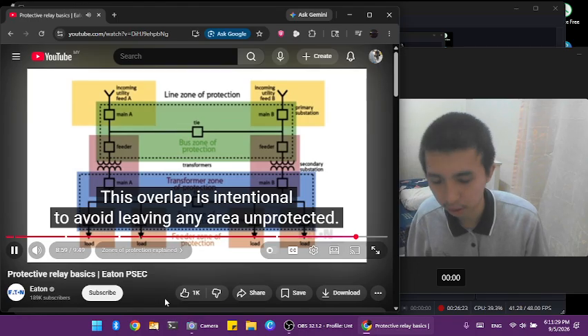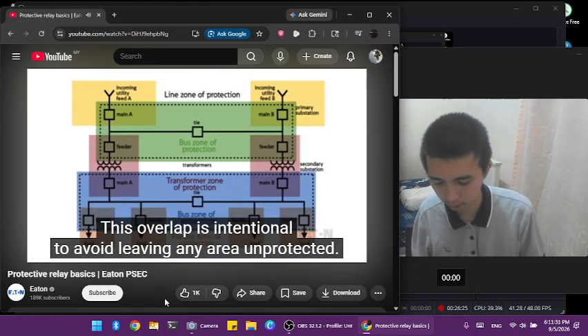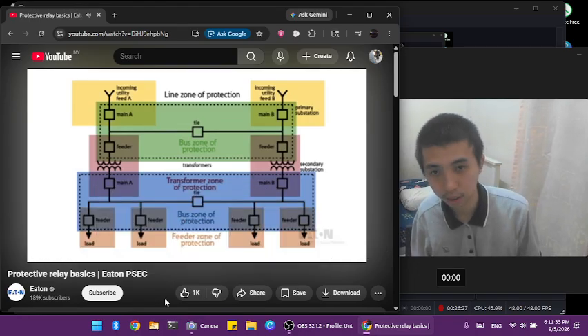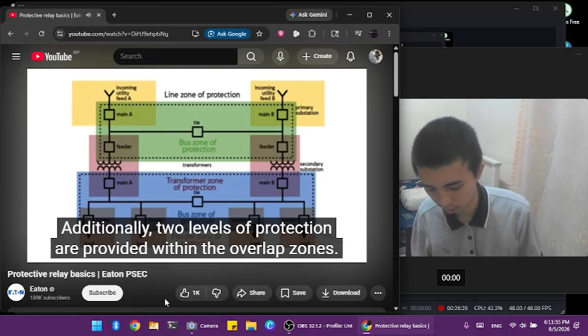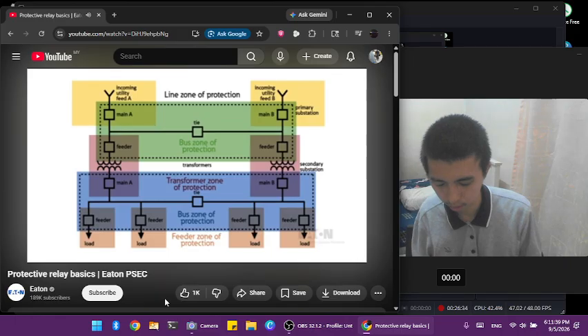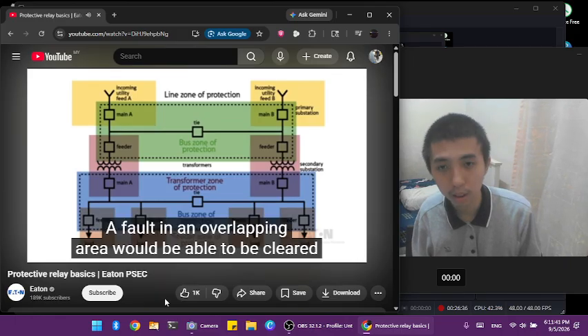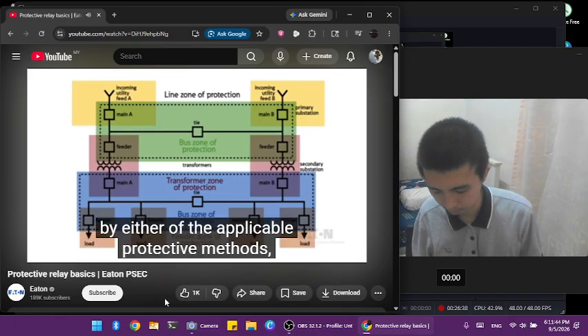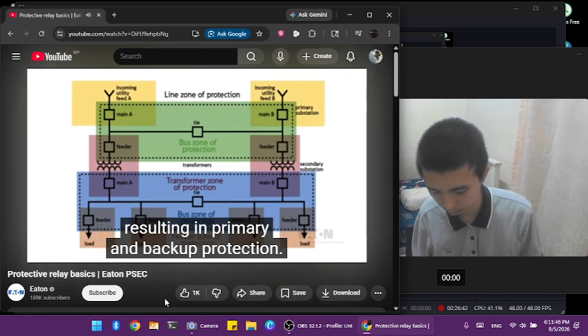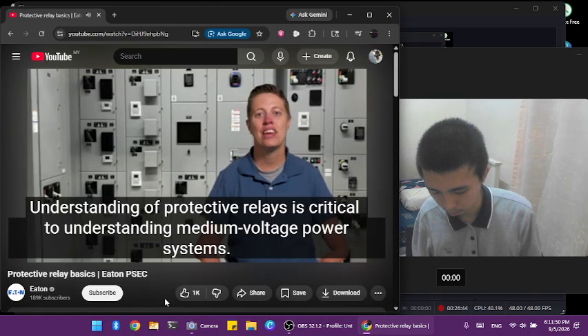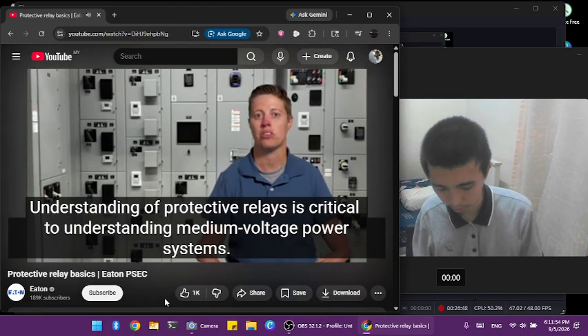This overlap is intentional to avoid leaving any area unprotected. Additionally, two levels of protection are provided within the overlap zones. A fault in an overlapping area would be able to be cleared by either of the applicable protective methods, resulting in primary and backup protection. Understanding of protective relays is critical to understanding medium voltage power systems.